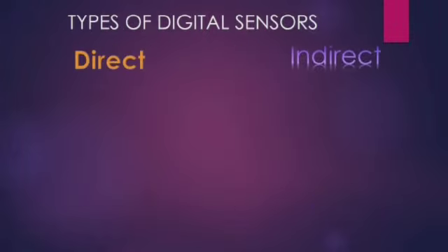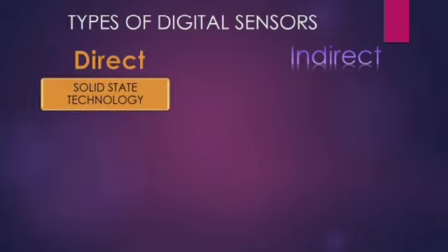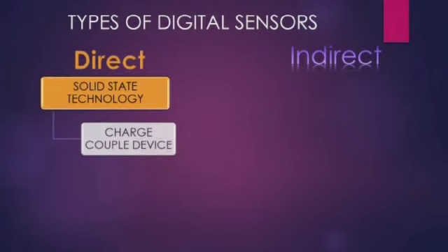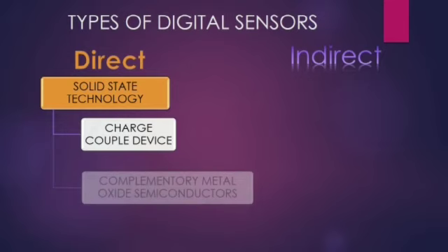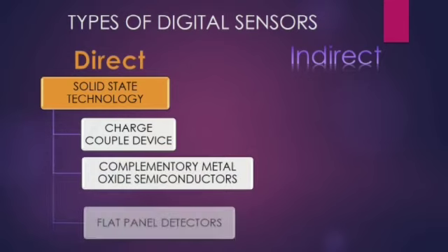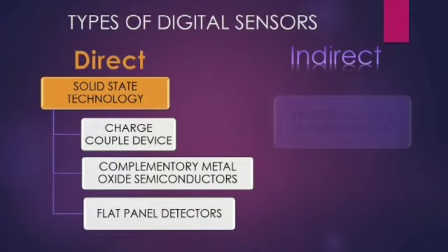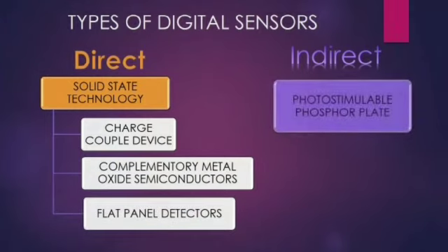So under the direct technique, we have solid state technology. These solid state detectors are further divided into charged couple devices, complementary metal oxide semiconductors and flat panel detectors. The indirect technique includes the photostimulable phosphor plate system.